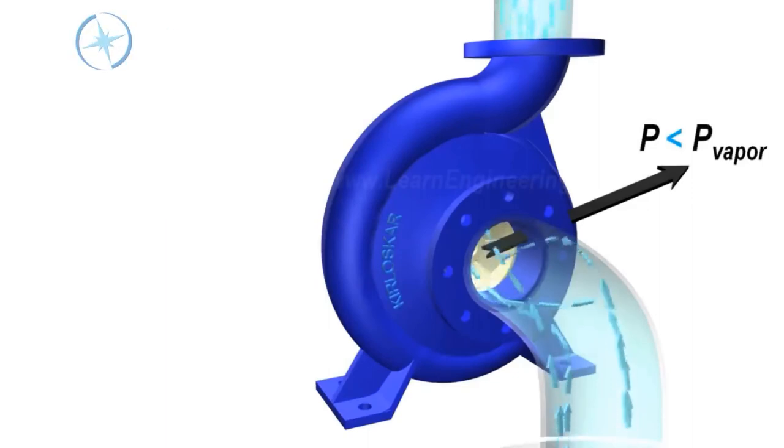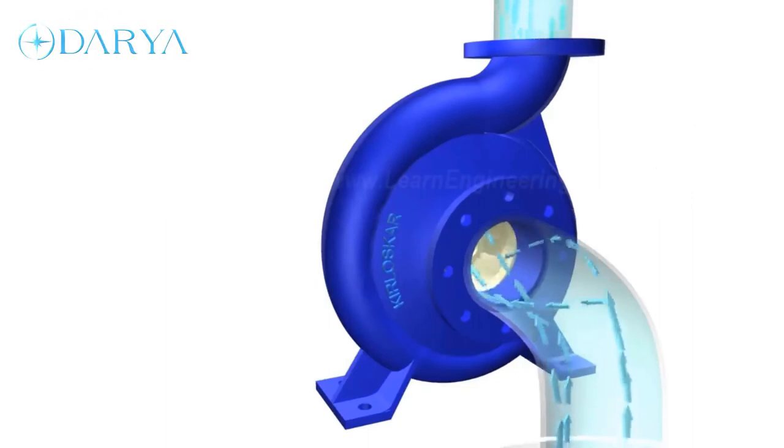If pressure at suction side of impeller goes below vapor pressure of water, a dangerous phenomenon could happen. Water will start to boil, forming vapor bubbles and spoil impeller materials over time. This phenomenon is known as cavitation.